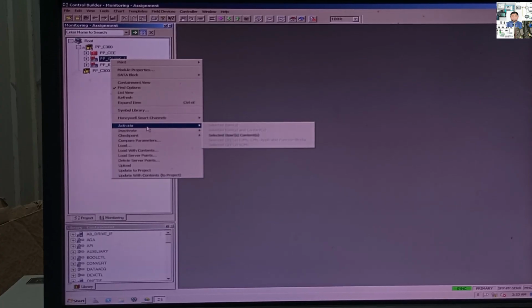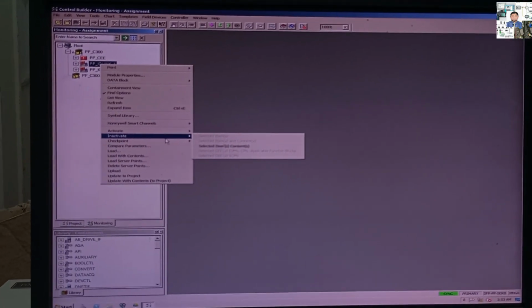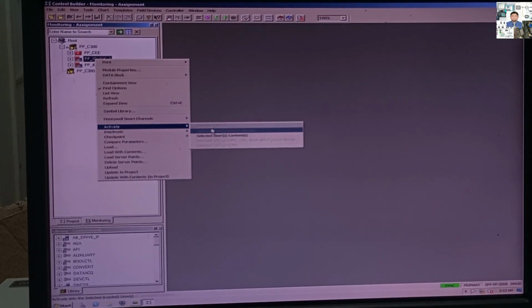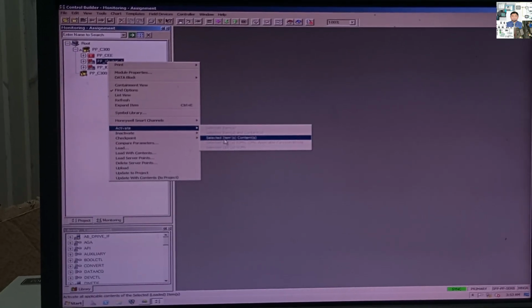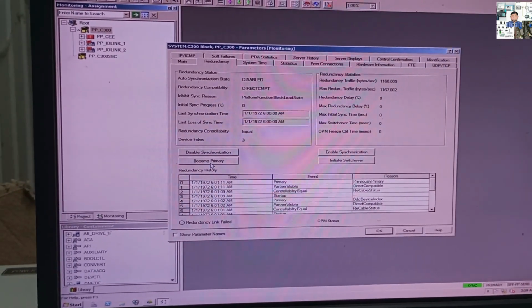First we have to activate this controller. You see, it is not active. The IO cards, IO link, and the control execution mode are all failed and not activated. We need to activate them. I will show how you can activate this, because it can happen suddenly and the synchronization fails.